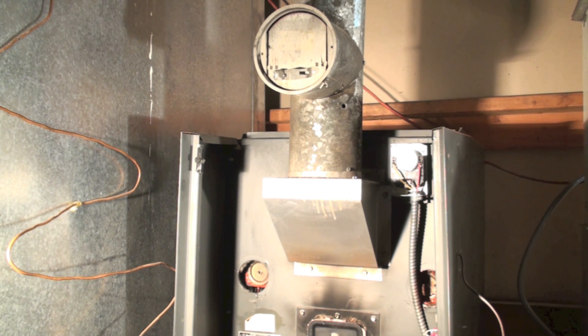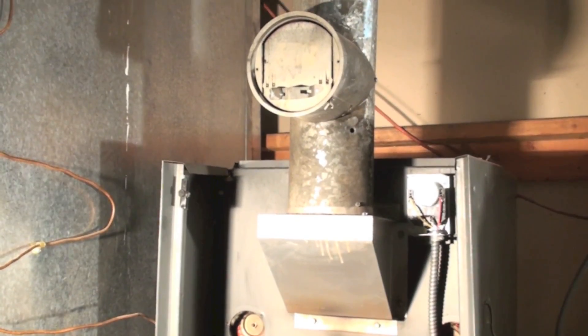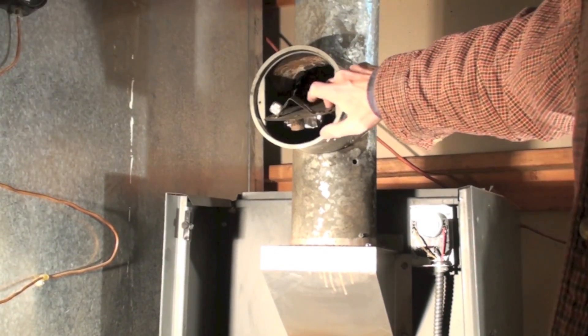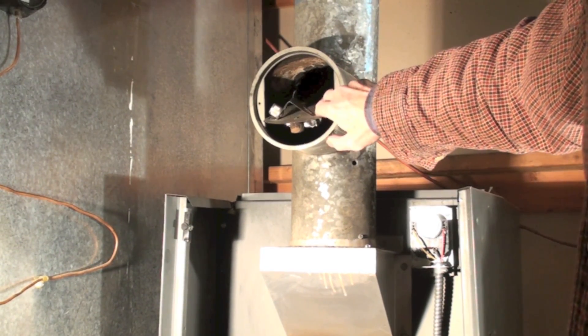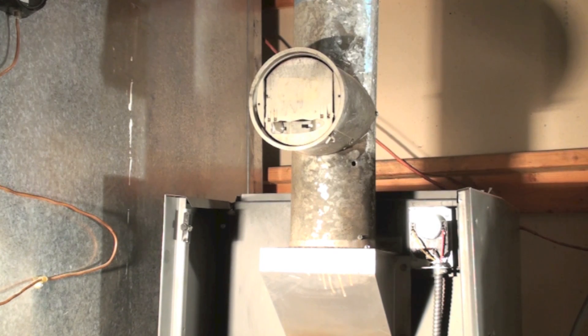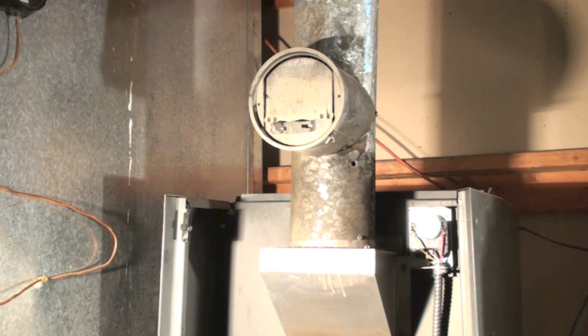That vent pipe is always under a negative pressure. Obviously I've got a great big hole right here in the barometric damper, and if there was a positive pressure here, the first place it would come out would be right there.